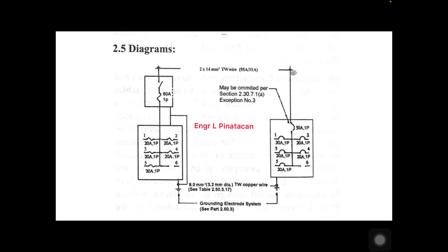The grounding wire is 8 mm² TW copper wire, verified per table 2.50.3.17. For the grounding electrode, we refer to part 2.50.3 of the Philippine Electrical Code. This is the standard for designing a small dwelling unit with not more than 6 circuits.